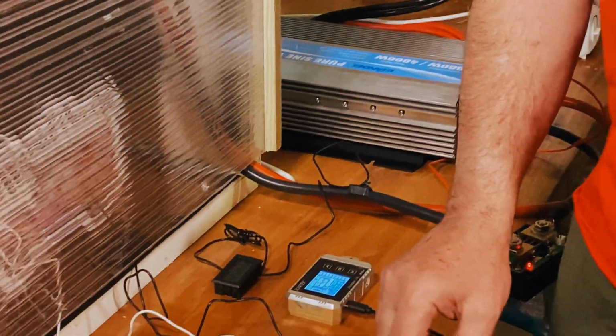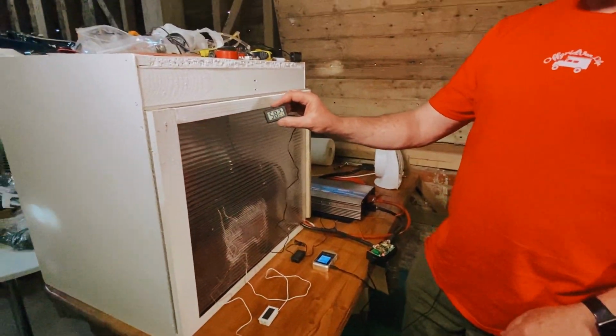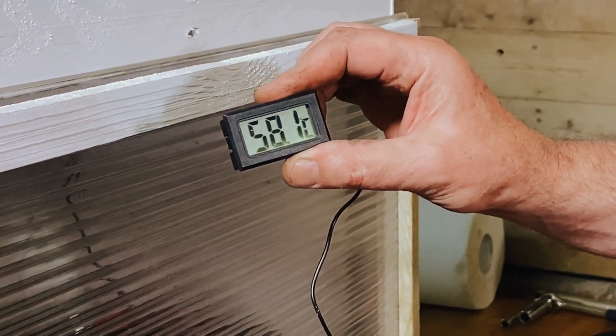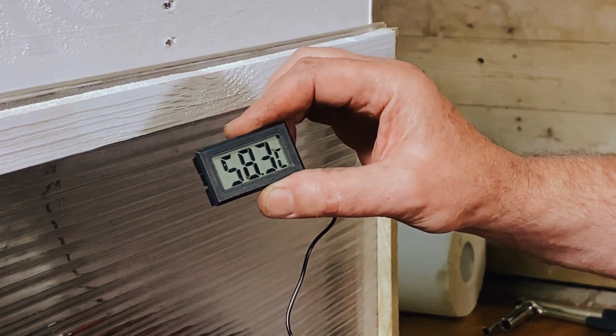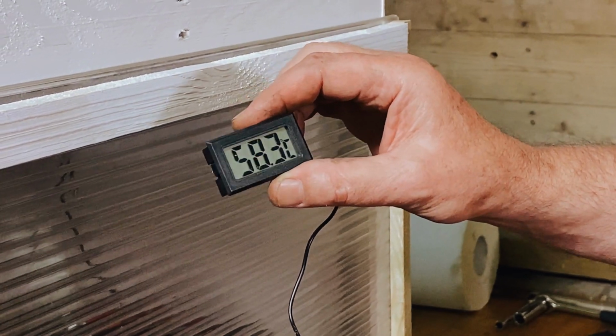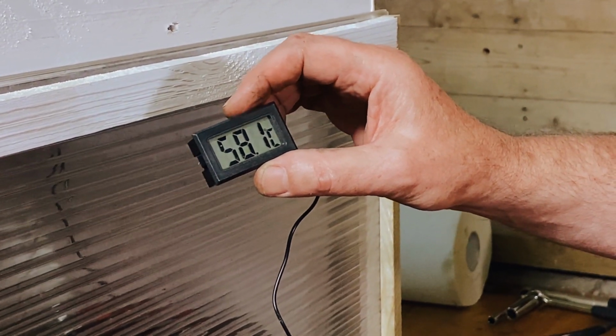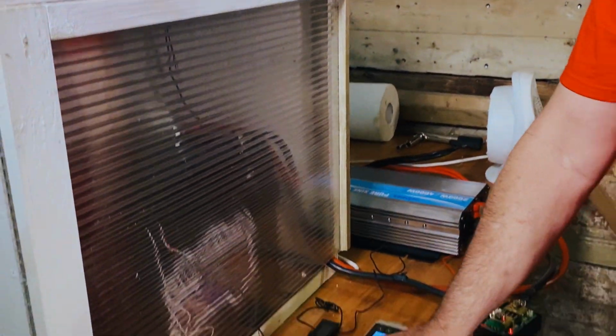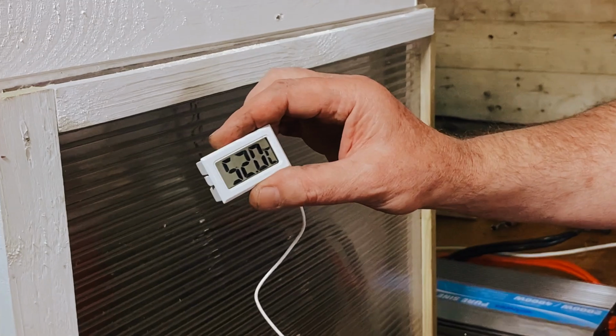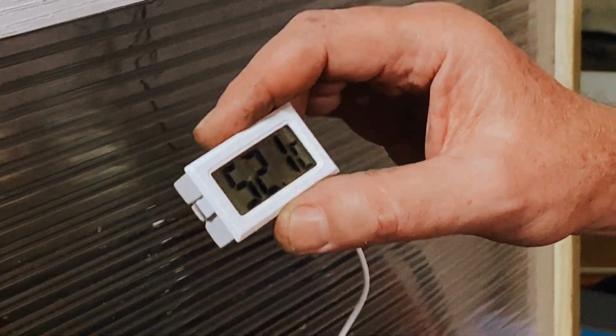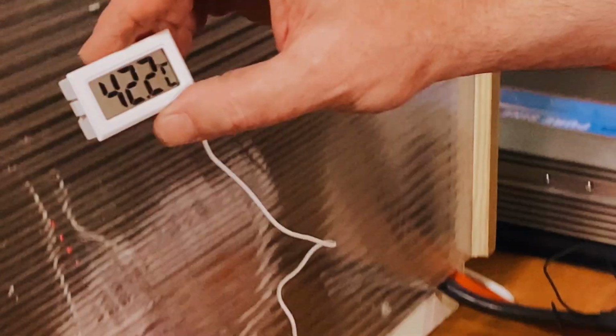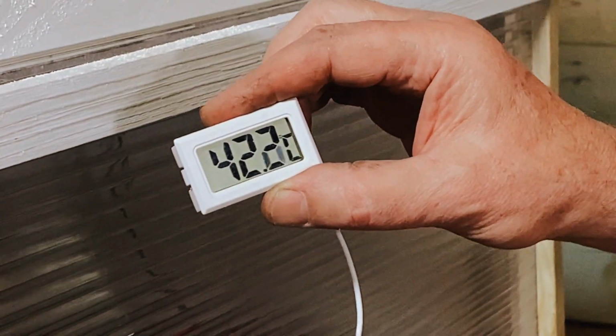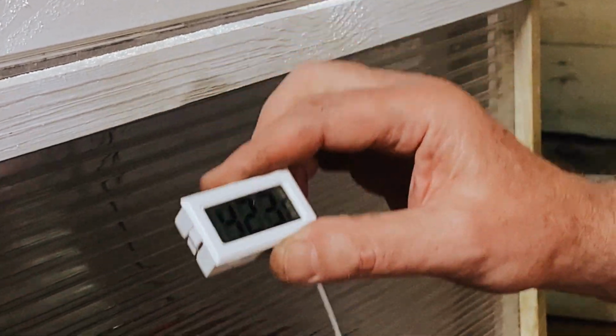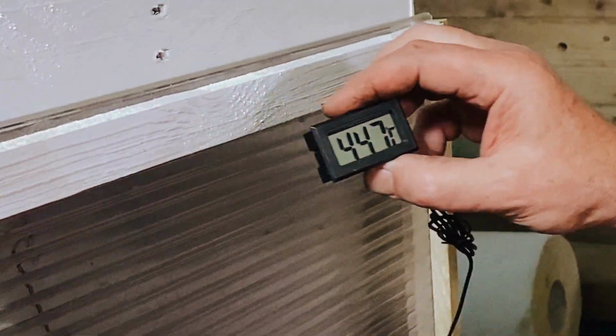Temperature wise, the highest is the negative cell, the main negative terminal, coming off the connection and the cell, just under 60 degrees, so not too bad. This is the main positive terminal, 52 degrees centigrade, and this is the main positive cable within the box, just to see how warm it gets, 42. And this is the external main negative, which has got to 44, 45.